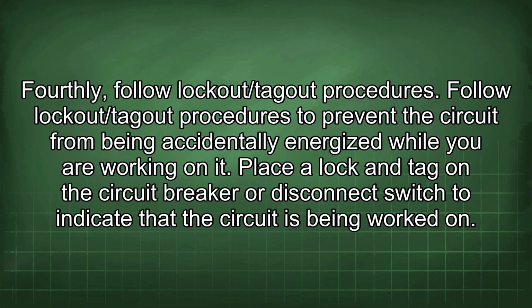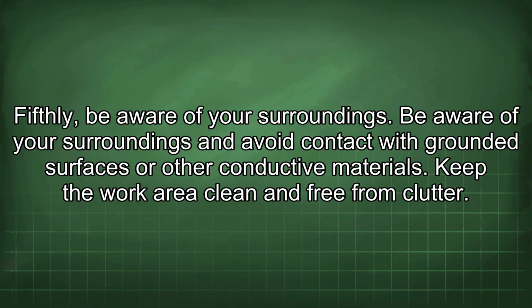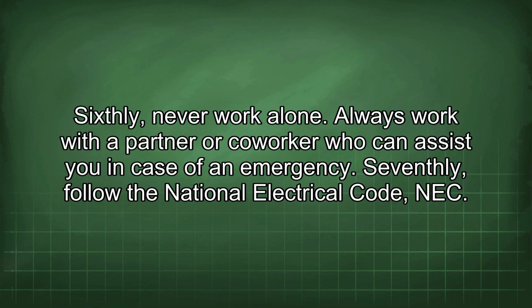Fourthly, follow lockout/tagout procedures. Follow lockout/tagout procedures to prevent the circuit from being accidentally energized while you are working on it. Place a lock and tag on the circuit breaker or disconnect switch to indicate that the circuit is being worked on. Fifthly, be aware of your surroundings. Be aware of your surroundings and avoid contact with grounded surfaces or other conductive materials. Keep the work area clean and free from clutter. Sixthly, never work alone. Always work with a partner or co-worker who can assist you in case of an emergency.